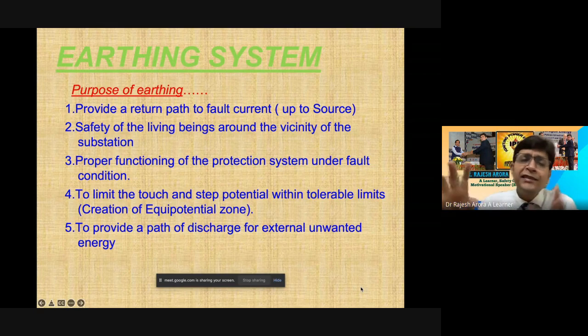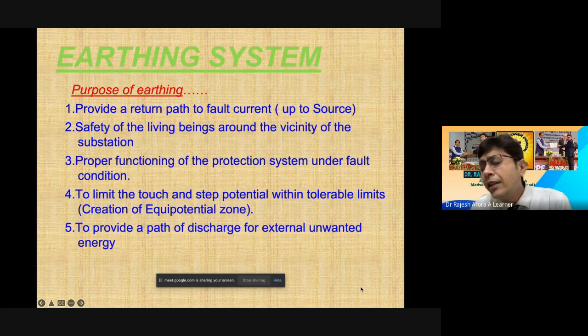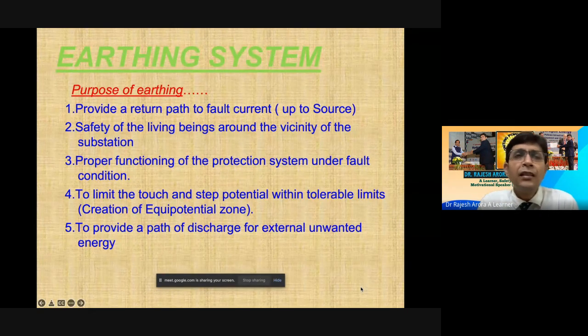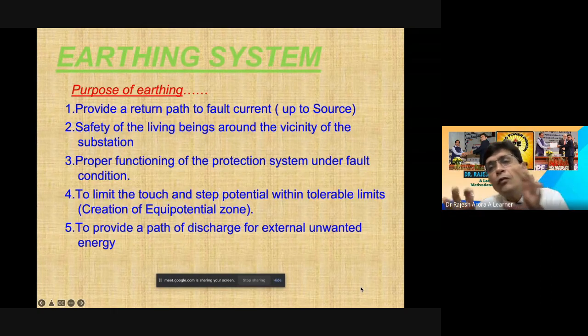You have to design all these things as per IS 3043, IS 732, CBIP manual 339. You can refer to IEEE 80. You can refer to IEEE 142. You can refer to IEEE 1100. You can refer to the NEC code. You can refer to IEC 62340. You can refer to BS 7430. Any regulations you can refer to, even the CEA regulations. The CEA Safety Regulation 2010 gives very good points related to the safety to be maintained.